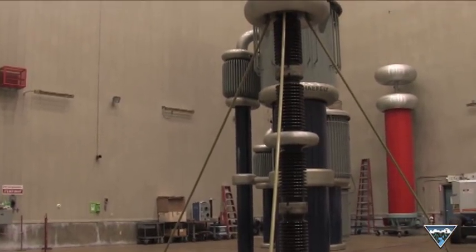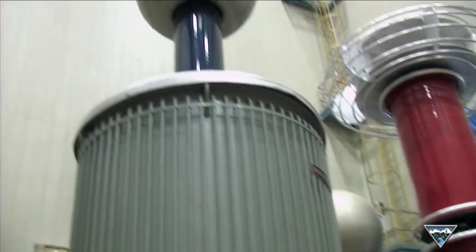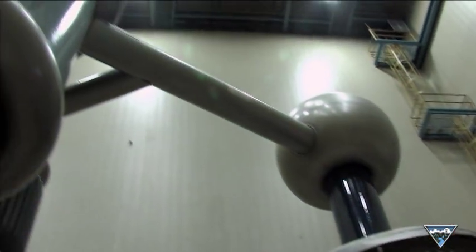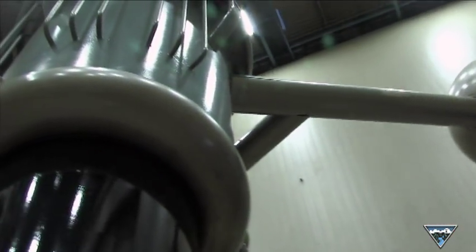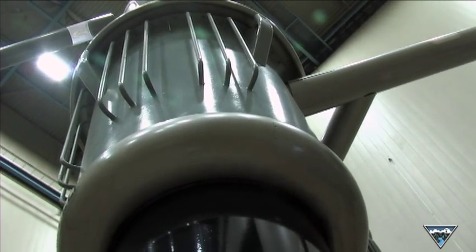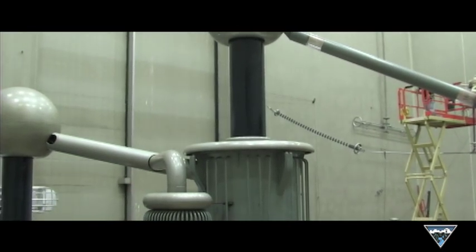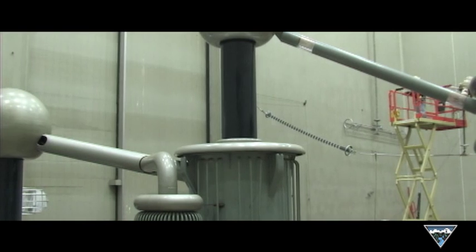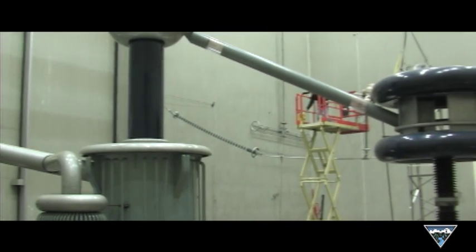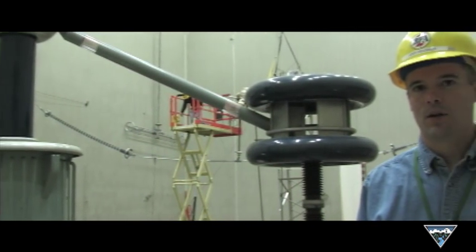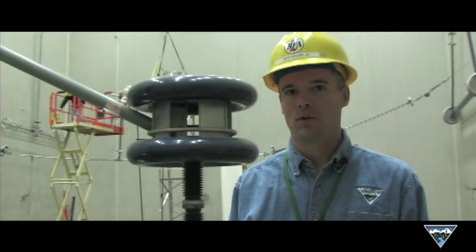Basically, the purpose of the high voltage lab is to make sure that we keep the power on the power lines. With the Cascade Transformer, we can produce 1.1 million volts, and we use that to test things like insulators, hot sticks, transformers, capacitors, bushings, to make sure that they can withstand those higher voltages.